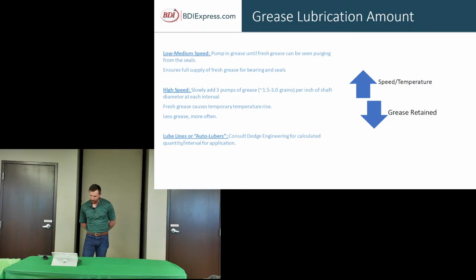And so you guys are going to be kind of in between, or the low to medium speed, but pumping in grease until fresh grease can be seen purging from the seals, and ensure full supply of fresh grease for bearings and seals. At high speeds, Dodge recommends slowly adding 3 pumps of grease per inch of shaft diameter at each interval. So on that previous chart, that would have been once every week.